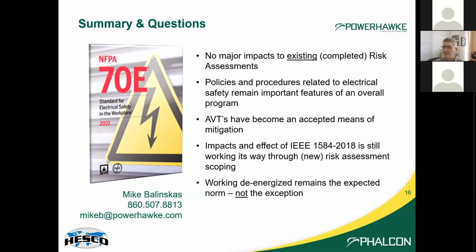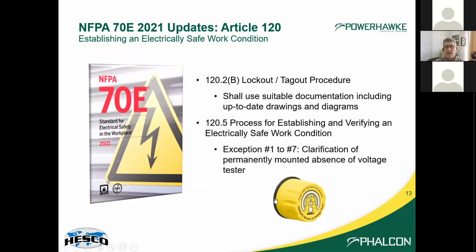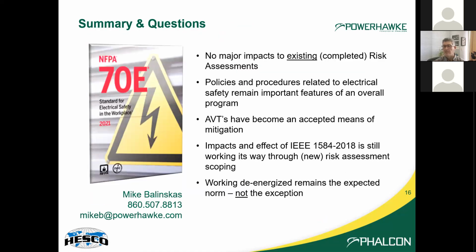Great. We did have a question come in: after de-energizing equipment, is it necessary to put on arc flash PPE to verify the equipment has been de-energized? Yes, a qualified person, again, that's key, you have to assume that it is energized until you verify that it is not. The interesting thing about this AVT that we showed here is that the device allows you to verify the absence of voltage without opening up the cabinet, without having somebody put their PPE on, and without having to use a test device. This is a pretty ingenious and well-engineered device that allows that to happen. But to answer your question, yes, a qualified person needs to assume that it is energized until you test that it is not. Okay, great.